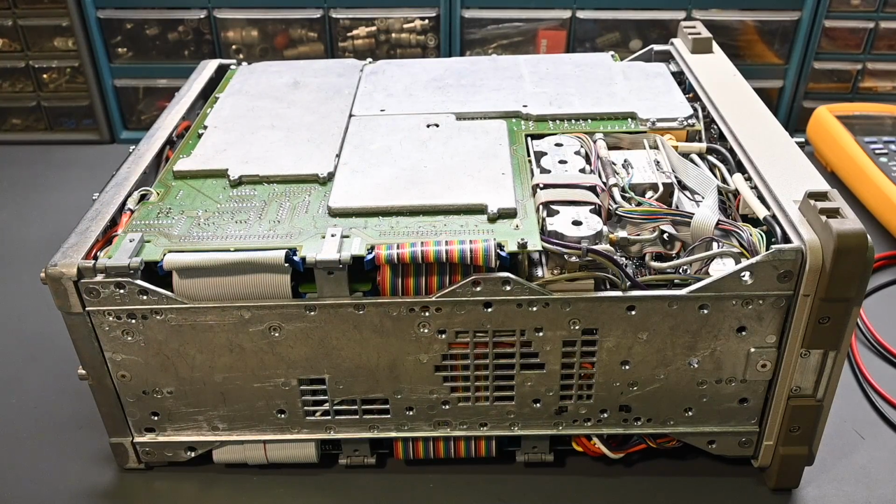Now, repairing the module myself is just not something that I'm going to be able to do. The internal components are wire bonded and they're absolutely microscopic in size, so it really does require specialized equipment to do any kind of internal work on the module. Now, back in the day, Hewlett-Packard and Agilent Technologies would have serviced this module, but nowadays Keysight Technologies no longer supports it and they won't work on it. So the best chance to repair this instrument is to find a used takeout module. That's exactly what I'll do. I'll get started on tracking down a replacement module.